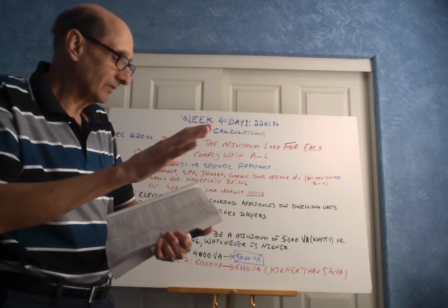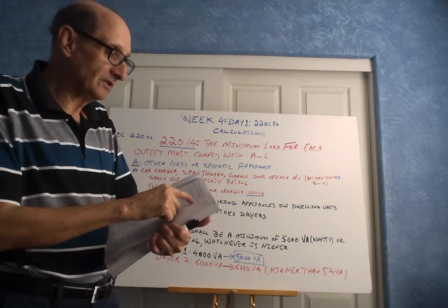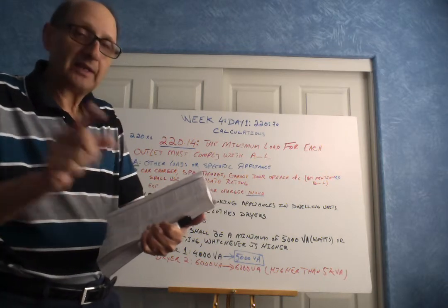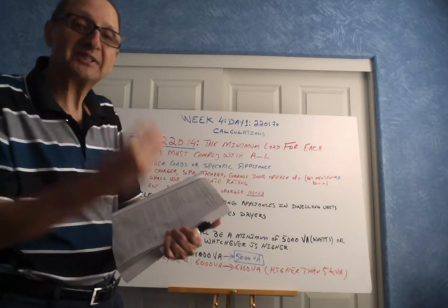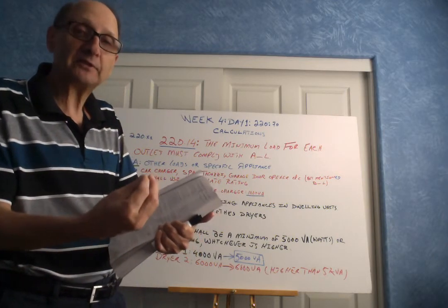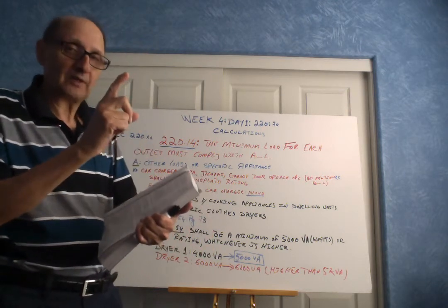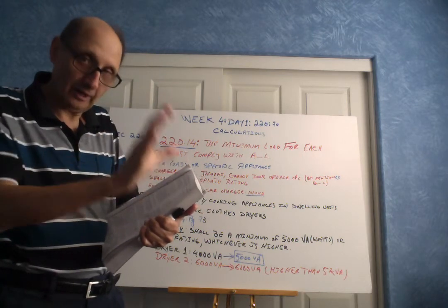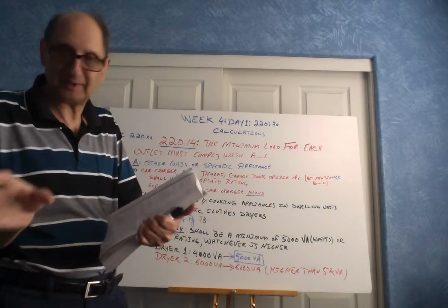We have two columns. One of them is number of dryers and the other one is demand factor. And look underneath, it says percent, so demand factors are in percent. If you have 1 through 4 electric dryers in your household, then the demand factor is 100%.